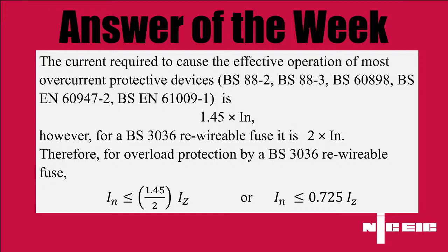Yes, in Appendix 4, under overload protection, it touches on that, to be fair. It talks about sizing conductors and protection against overload using a rewirable BS 3036 fuse, and it talks about that factor rating of 1.45 divided by 2 equalling the 0.725. So it is actually in the regs, and you can find further guidance in Appendix 4, I think on page 424 of the original brown cover book.